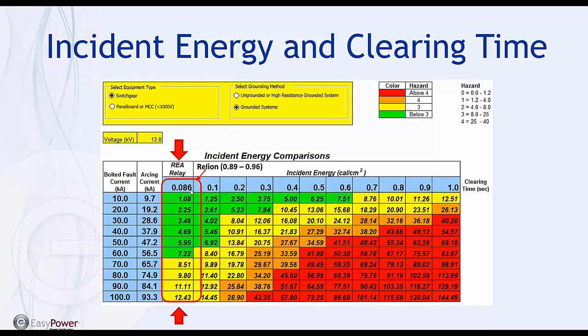It's negligible compared to the breaker time, which is 5 cycles here, or 0.083 seconds. So you can see that it's the fastest operating time that you can have. Our ReliOn is very close. We're somewhere between the first and second column for the built-in arc flash feature ReliOn. Depending on the measurement mode, whether it's RMS or DFT, it'll be just a little bit slower, but not that much slower. So it's still a pretty good choice.